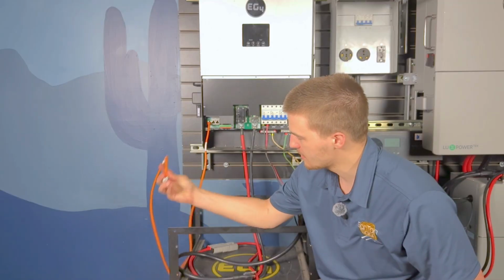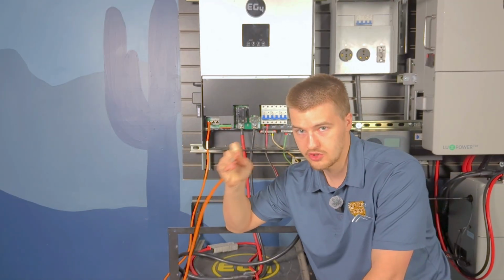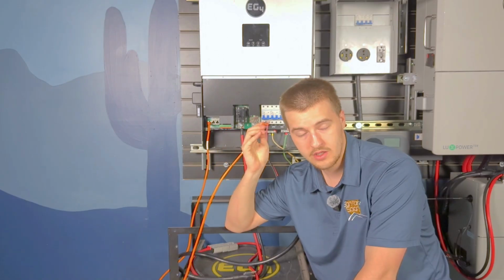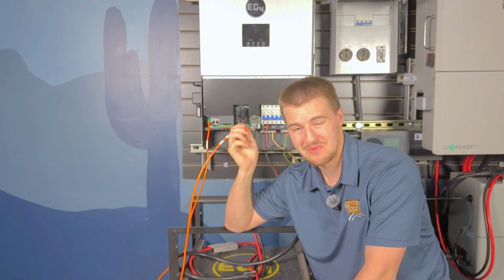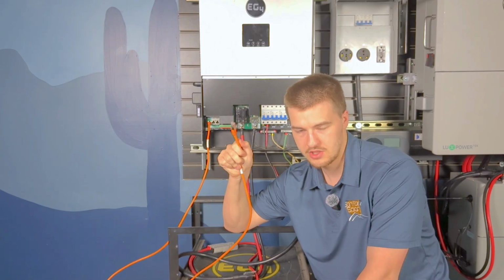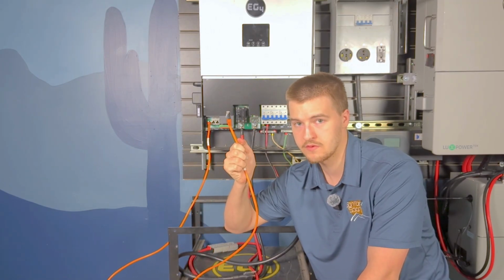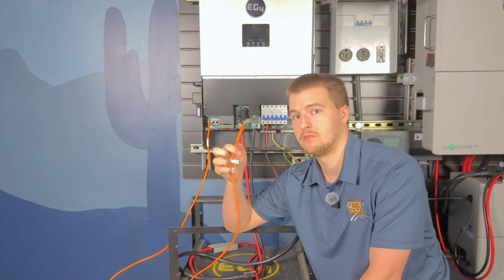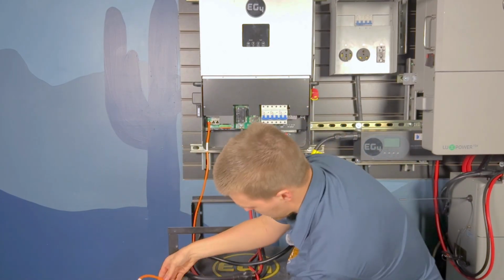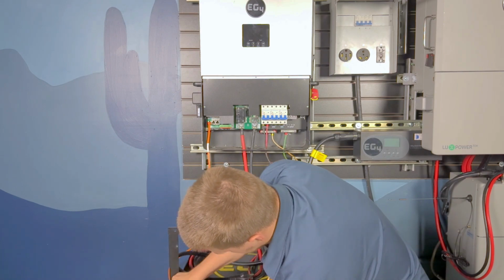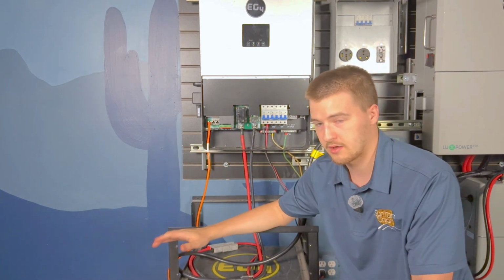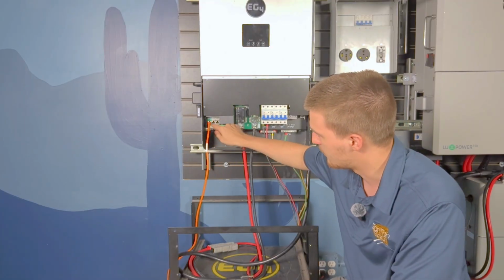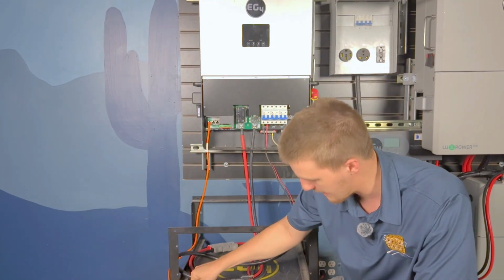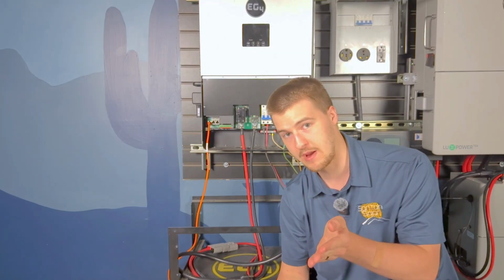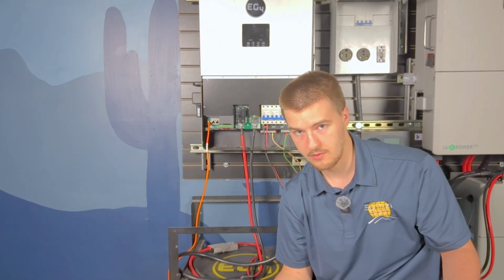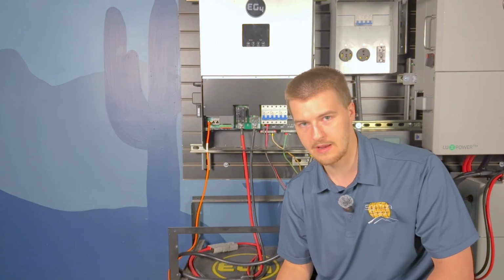The orange cable will always go to the CAN port. Only in some cases will it go to the RS-485 port, depending on the situation. If you're watching this video because you just bought EG4 equipment, that doesn't matter - this is what you need, to the CAN port right here. Then you might be saying, what else do we do? Nothing, that's it, easy as pie. Battery BAT COM port to the CAN port on your master battery, which is your first battery in your line if you have more than one battery. If not, then still put it in the CAN port.